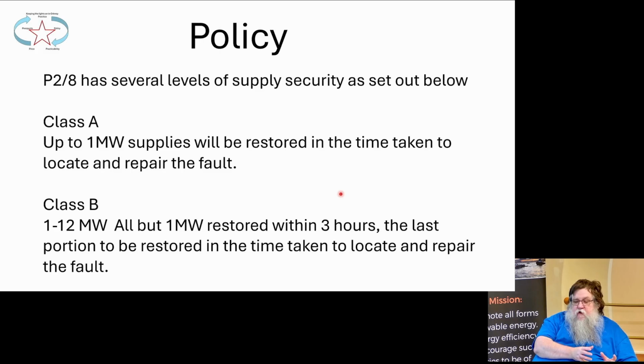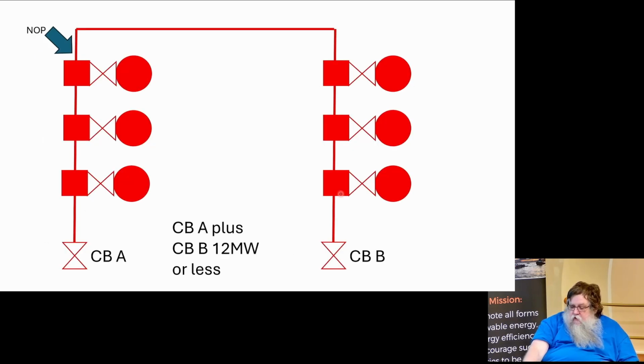And for that area, you've got to comply with that. You've got to get all but 1 megawatt restored within 3 hours. And the way it's done is you start with 2 circuit breakers at the substation, multiple substations, each one of which could be up to 1 megawatt. And you have what's called a normal open point. And a normal open point is just a switch which is open.